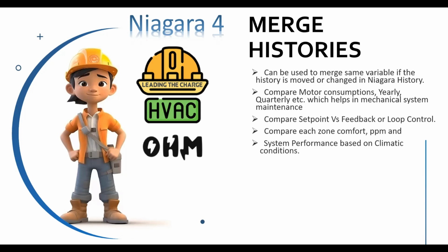Today I will give an example in Niagara of how we create and merge histories. I'll create a sample temperature, create a history on that, then merge the histories and produce an output. The output can be in different formats. You could do it manually by exporting into a spreadsheet in CSV format. You could also generate a weekly or monthly report, and that report can be sent through email.